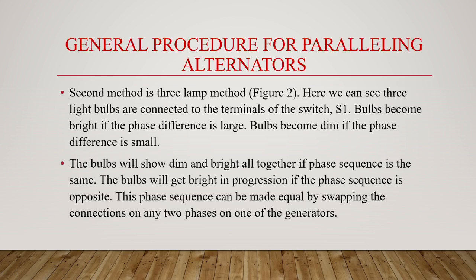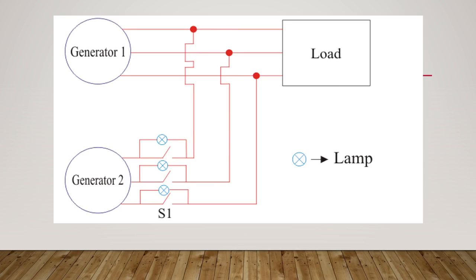Three light bulbs are connected to the terminals of the switch S1. A bulb will become bright if the phase difference is large, and bulbs will become dim if the phase difference is small. So bulbs will show dim and bright all together if the phase sequence is the same. Bulbs will get bright in progression if the phase sequence is opposite, and this can be made equal by swapping the connections on any two phases of any one of the generators. So bulbs show dim and bright all together if the phase sequence is the same, and bright in progression if it is opposite, and they can be made equal by swapping the connections on any two phases of one of the generators.